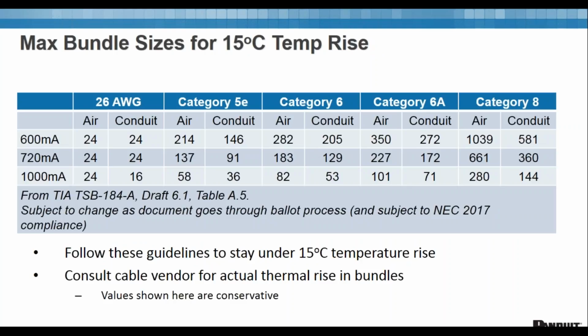This is now taken out of the TSB 184A draft, and it's the max bundle sizes for 15 degrees C temperature rises. You can see this looks at a variety of different cable types, all the way from 26 gauge up to Category 8, and it's looking in 2 different environments, in air and conduit. So the rule of thumb we'll give you here is that if you don't have any additional guidance from the vendors you're using, these are good numbers to go with for what people recommend.